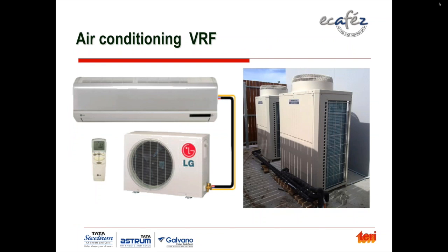Now, air conditioning. This is a simple example of air conditioning in a plant, which was essentially used for space air conditioning. One of the process areas had to be cooled, and they earlier had this kind of split air conditioning system, as you can see on your screen. It was changed to a variable refrigerant flow, VRF, system, also called variable refrigerant volume, VRV, which is essentially the same term.